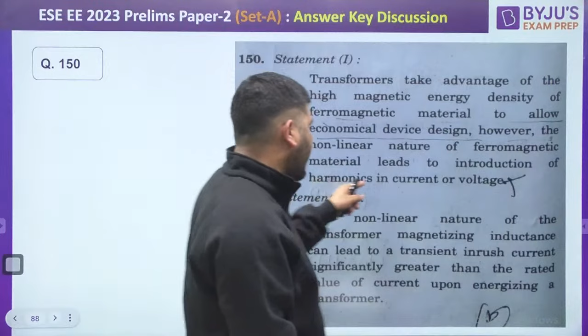We know the BH curve. Generally we operate the transformer at this point - the flux density should be at this point, and the H should be at this point. Why is it so? Because if the flux density is higher, you need less core cross section area for a given flux, since we know that phi is equal to B times A.